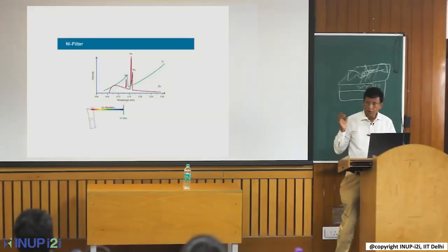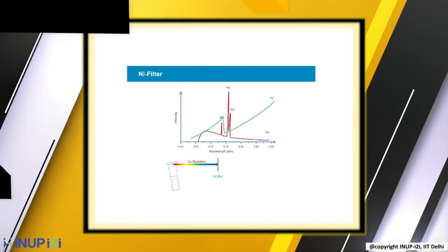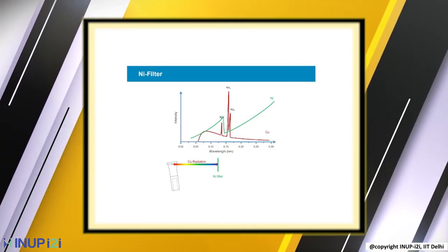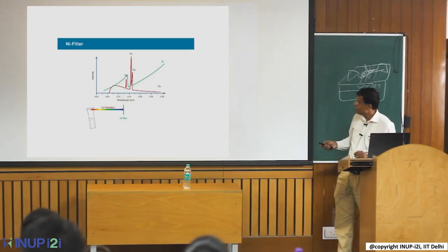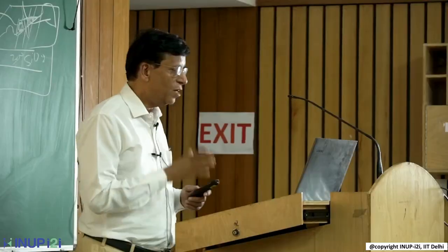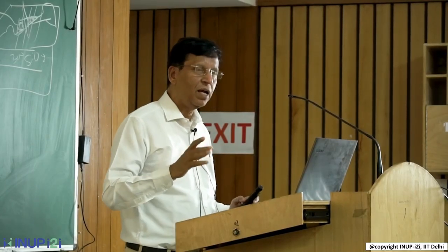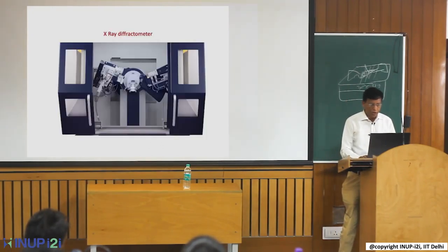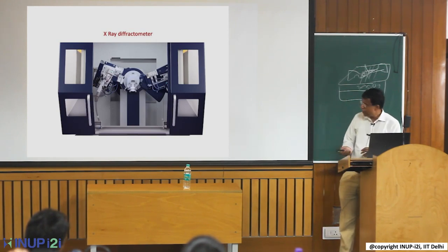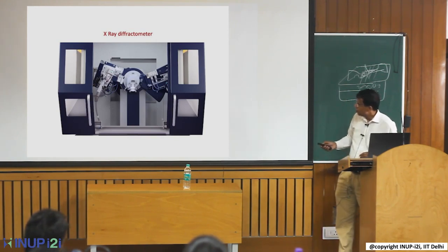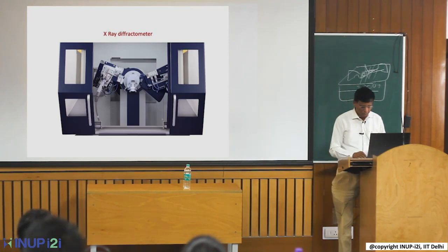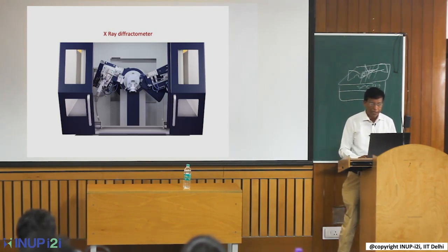For the instrument we use here, we use a nickel filter which eliminates all other radiations, leaving just the K-alpha 1 and K-alpha 2 lines. We know very precisely the wavelength of K-alpha, so we have the lambda value and from there we calculate the d-spacing. The instrument has an X-ray generator, a sample stage, and a detector that moves to record reflected X-ray at different values of theta.